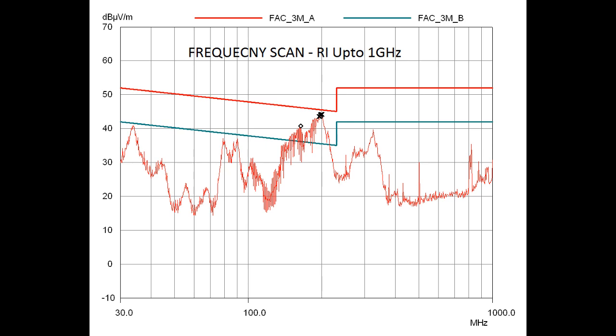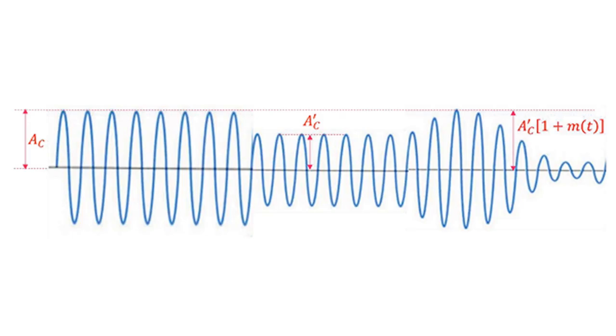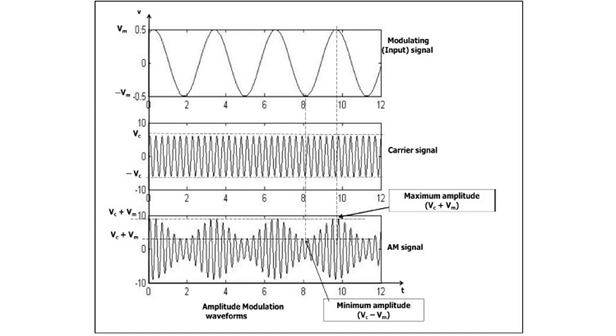Specified by the standards, the intensity of the testing field is represented as a value of an unmodulated signal. This signal is modulated by a sine wave at 1 kHz with 80% modulation depth when testing electromagnetic susceptibility. The real threat when radio frequency fields are radiated is simulated for the equipment under test by this modulation.